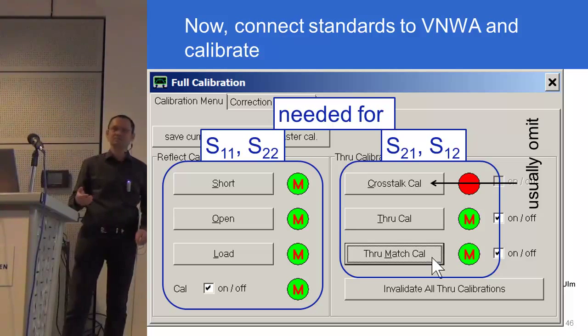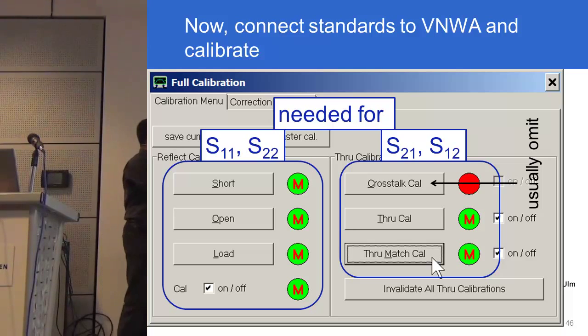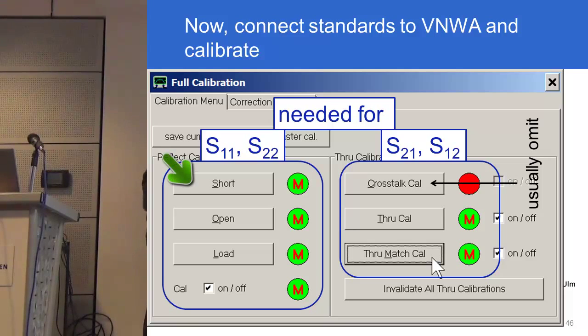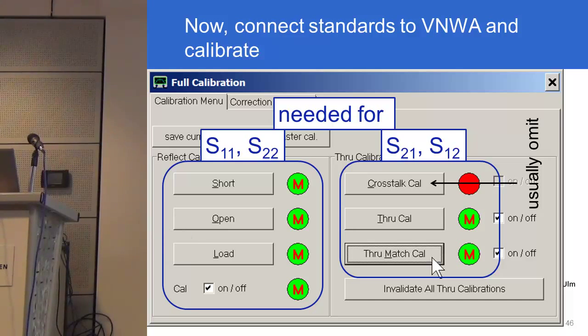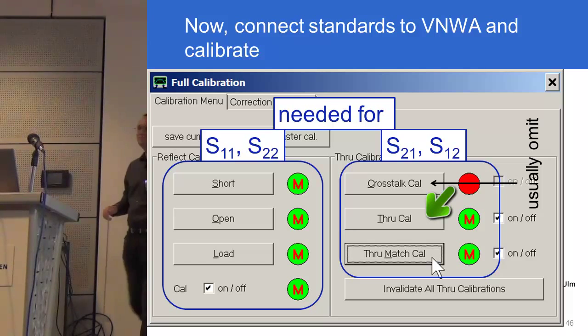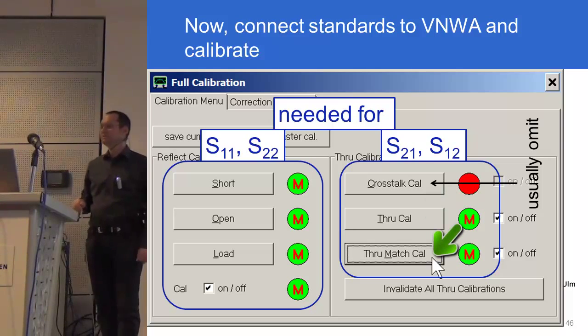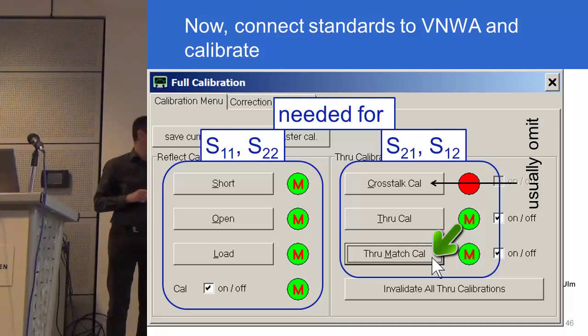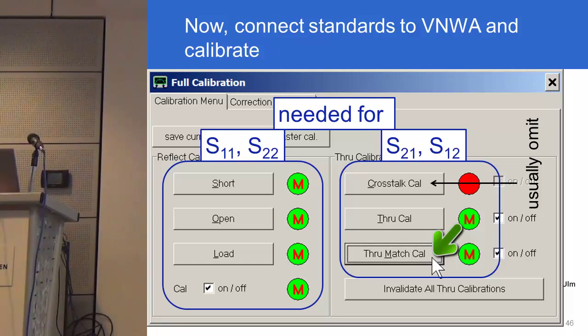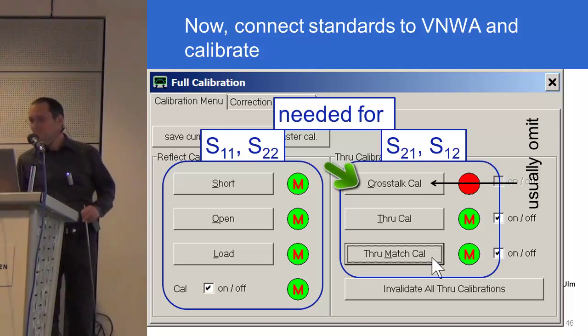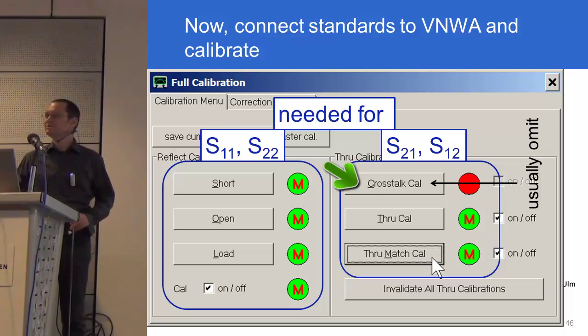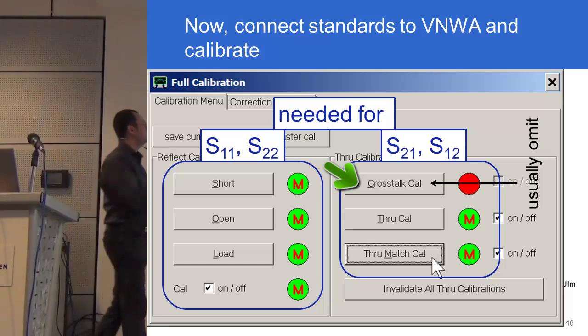After entering the calibration standard data and saving calibration settings to a file, we open the calibration menu. After fitting the short calibration standard, click on the short button; then fit the open calibration standard and click on open; then fit the load calibration standard and click on load — which concludes reflection calibration. Next, connect the TX and RX port via the through adapter and click on through calibration, then through match calibration — the latter to compensate for reflection at the RX port. The RX port is supposed to be 50 ohm but is not, so mismatch errors can be mathematically calculated and corrected.